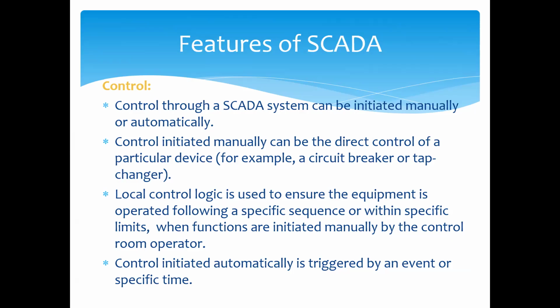Control initiated manually can be direct control of a particular device, for example, a circuit breaker or a tap changer. Local control logic is used to ensure the equipment is operated following a specific sequence or within a specific limit, when functions are initiated manually by the control operator. Control initiated automatically is triggered by an event or a specific time.